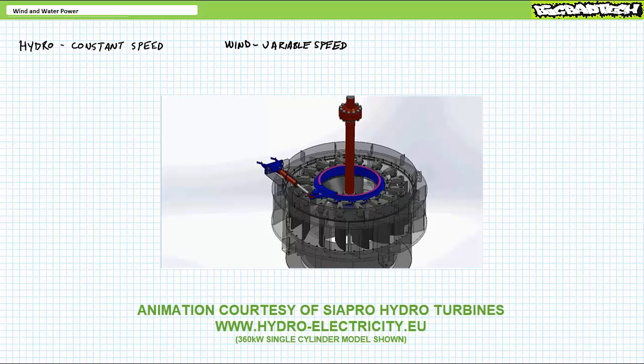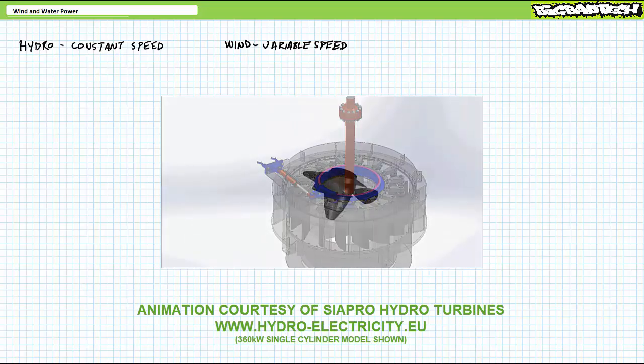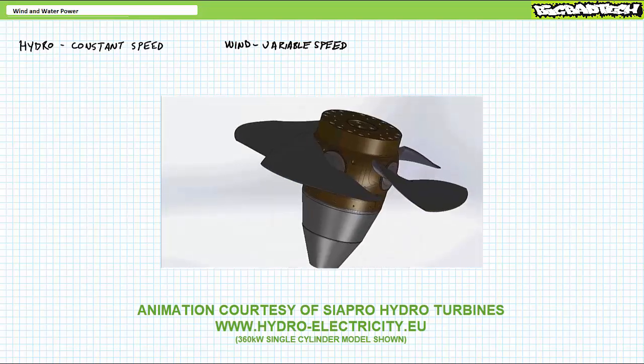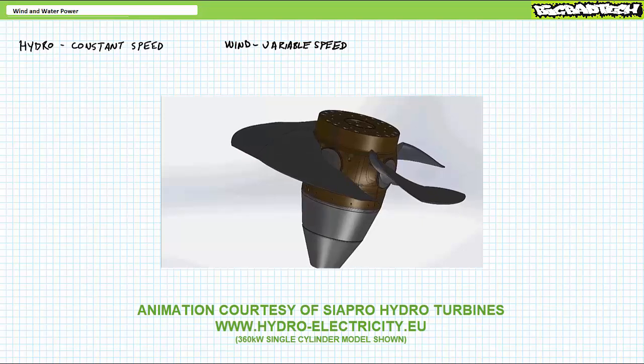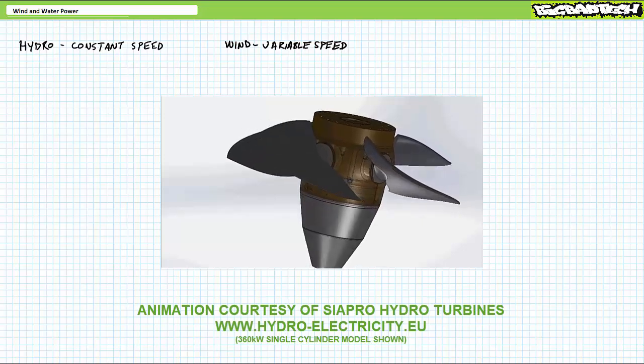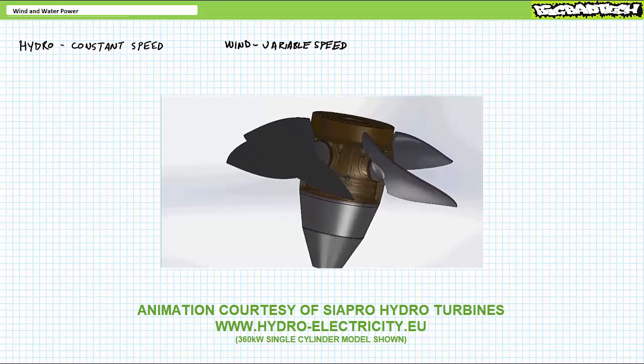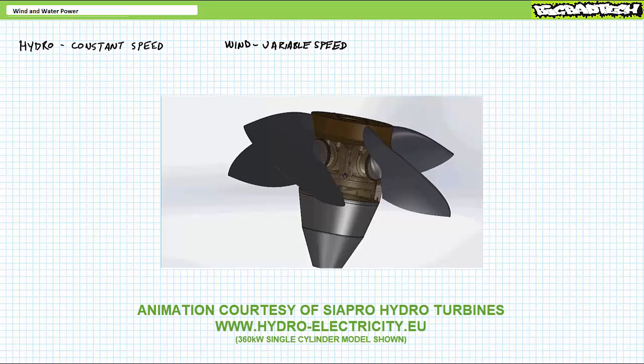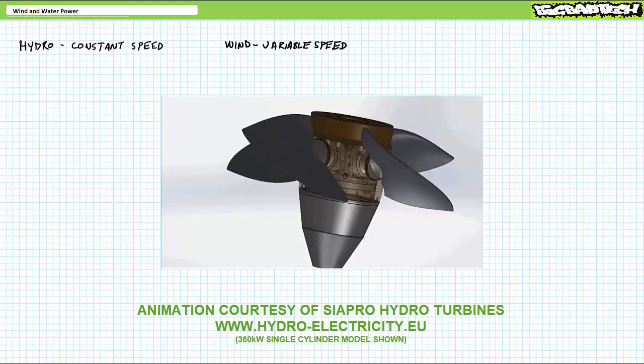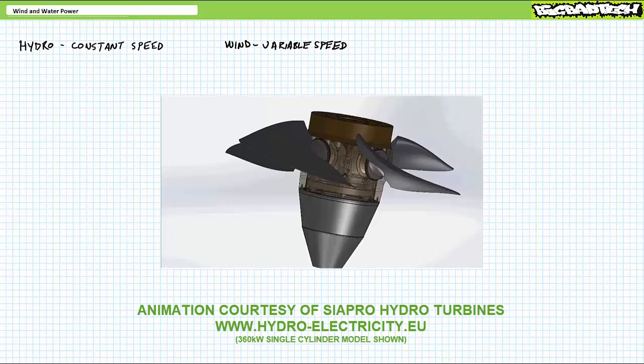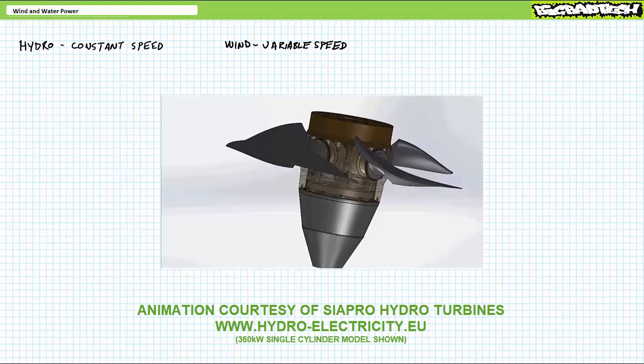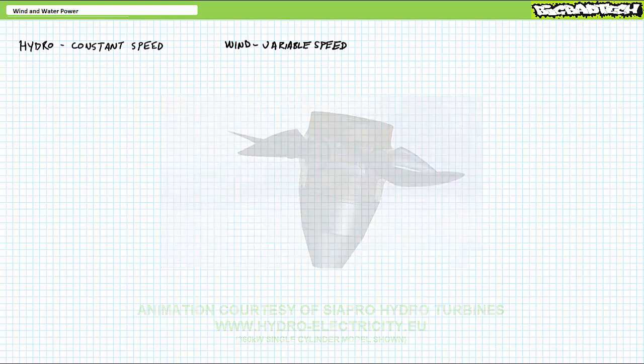In addition to modulating the flow rate using the wicket gates, a Kaplan turbine can additionally pitch the blades as do wind turbines to capture more or less of the incoming flow. If you think about it, the primary responsibility of a hydropower turbine control system is not to respond to wildly changing input as would a wind turbine, but rather keep input inside a defined range that maximizes efficiency.